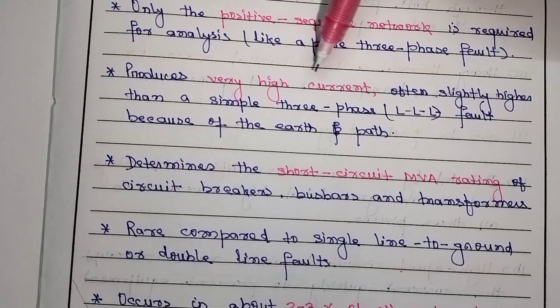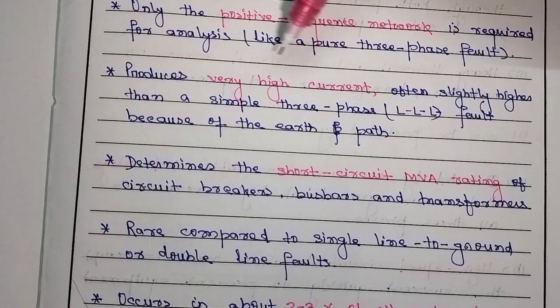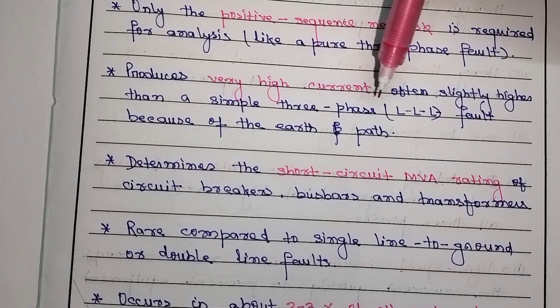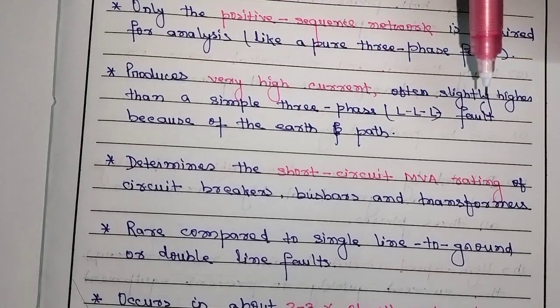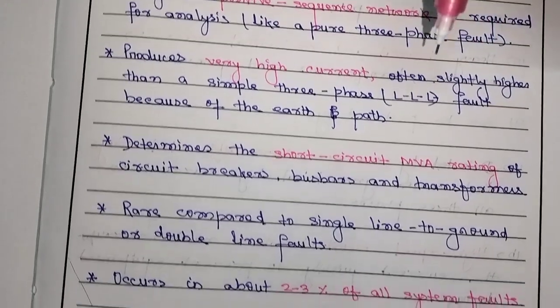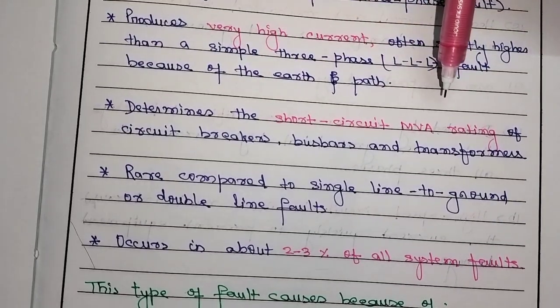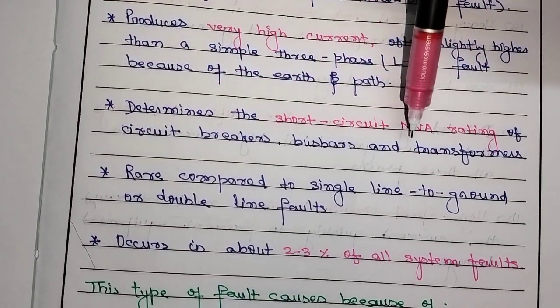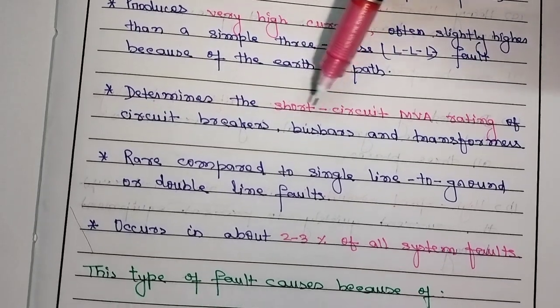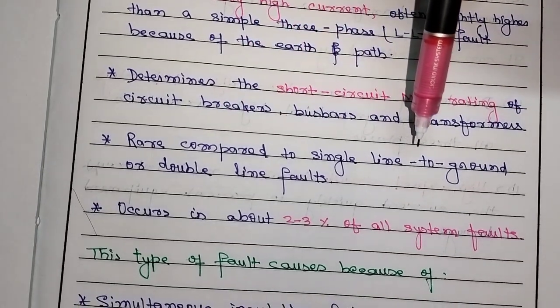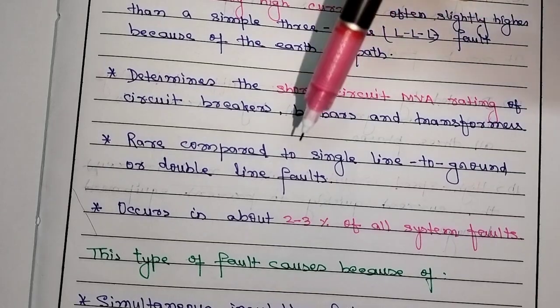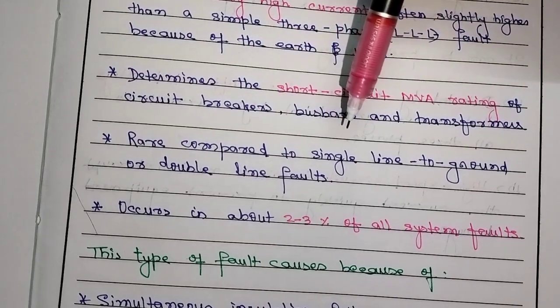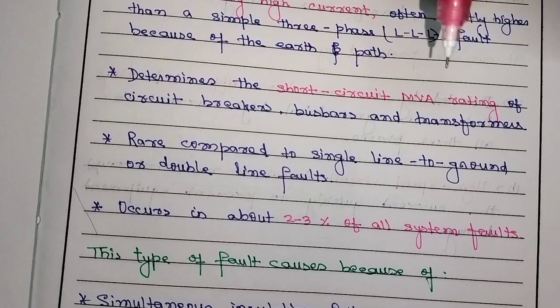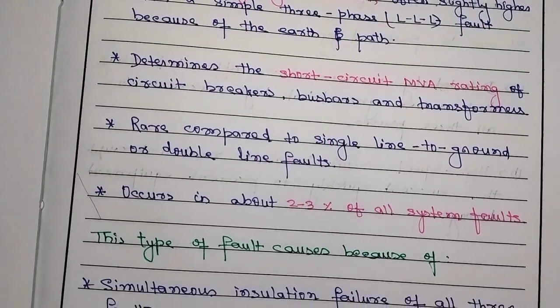It produces very high current, often slightly higher than a simple three-phase fault because of the earth path. It determines the short circuit MVA rating of the circuit breakers, bus bars and the transformers. Already we have discussed this point. It is rare compared to the single line to ground or the double line to ground fault. It occurs very rarely, whenever all three lines get touched and the fault occurs. It occurs in 2 to 3% of system faults.